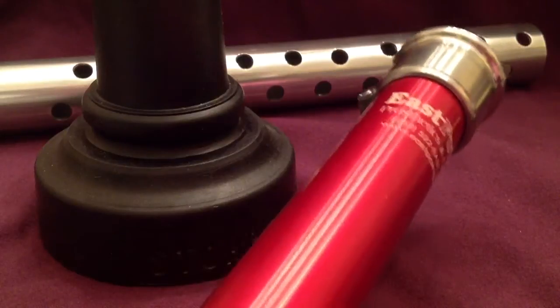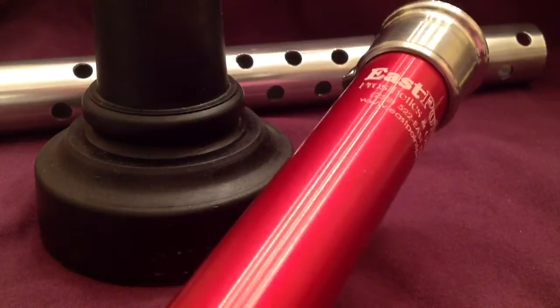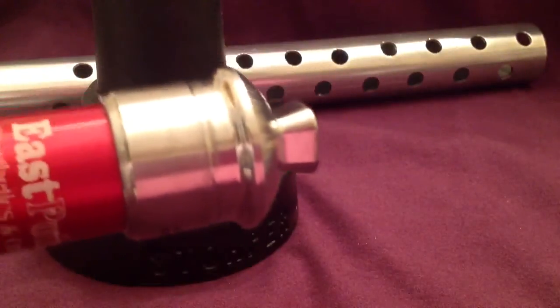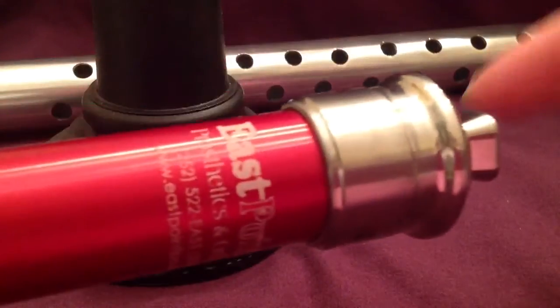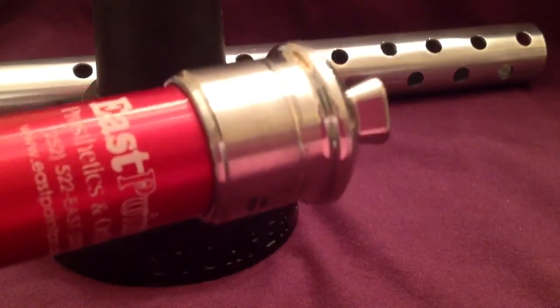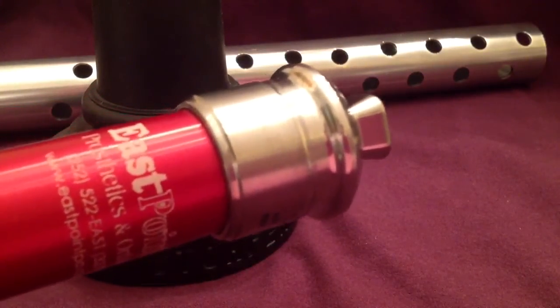The main components: we just have a 17-inch regular 30 millimeter pylon. I chose to put the 30 millimeter sleeve inside the other one going towards the top so that you can use regular 30 millimeter components to change things up at the top. If you have a particular length issue or you're matching it up to a particular knee, sometimes you might need to change the pyramid adapter out. I keep the male pyramid on there most of the time because most of my check sockets will have a female rotatable pyramid, and that's what we carry over into the definitive to attach to knees.